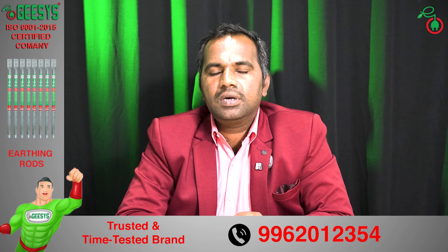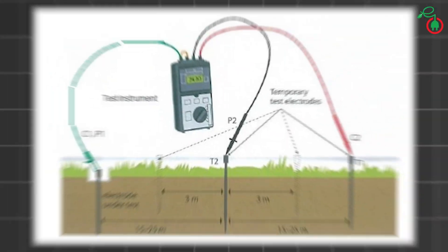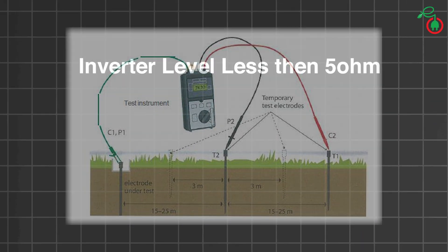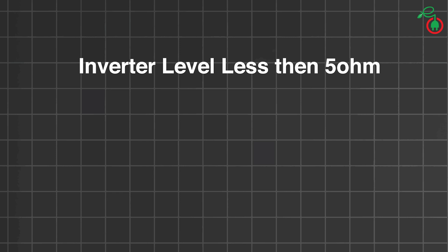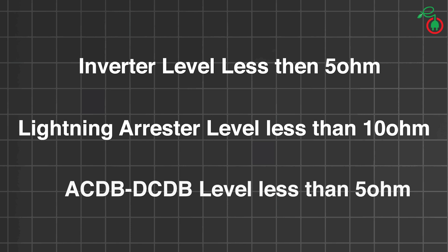When it comes to target resistance values: at the equipment level and inverter level, you should have less than 5 ohms; at the lightning arrester level, you should have less than 10 ohms; and at the ACDB, DCDB, and other equipment, you should have less than 5 ohms. Lower the resistance value, the better the dissipation of fault current.